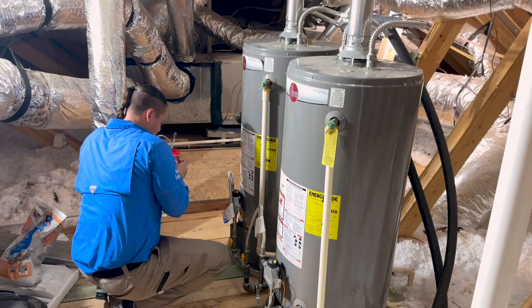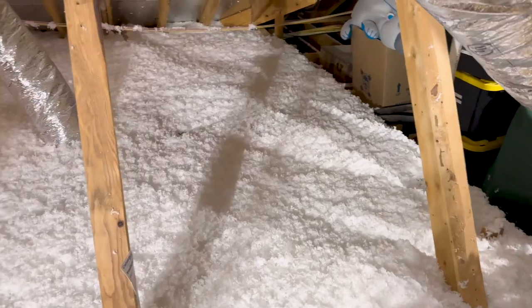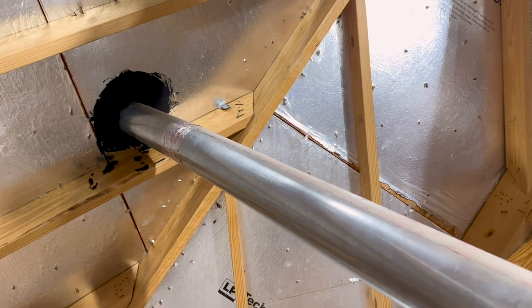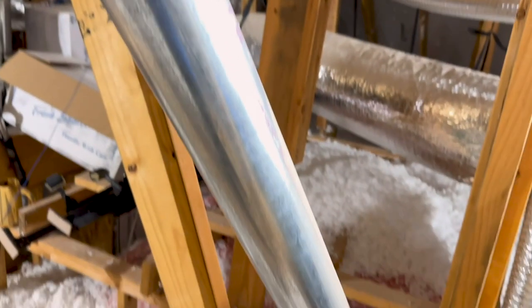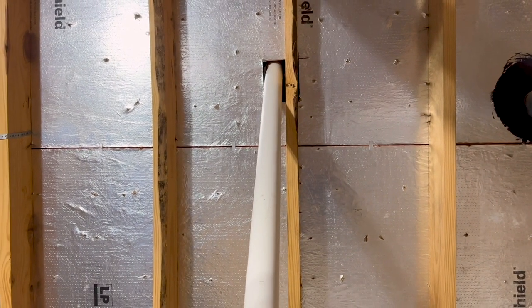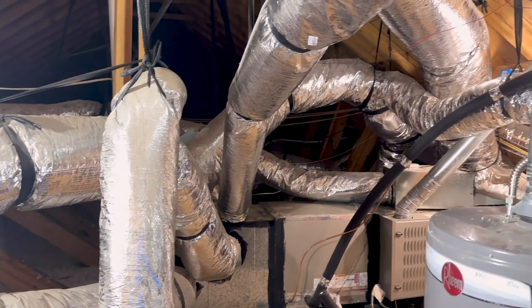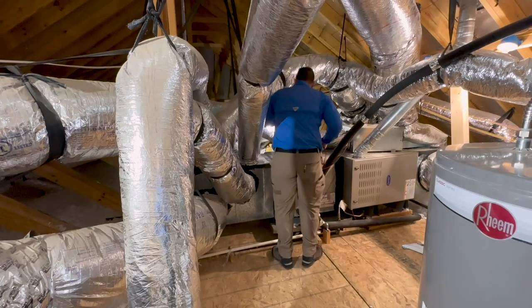This was a one-year warranty inspection, so the client has lived here for a year. What we always do is go through and do everything we do on a normal inspection, but we're re-assuring them that everything is holding up well. We check all the penetrations again, do gas leak tests, and look at every possible spot we can. We don't treat one-year warranties any differently — we're picky on every inspection. You can see Tyler taking a look at the ductwork, making sure everything stayed fastened well and checking for separation around the coil box.